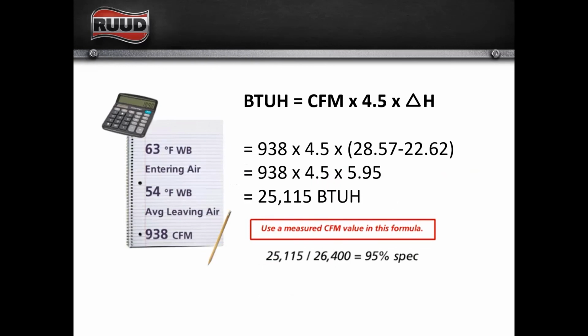So 938, we're going to plug that into our formula, right? BTU per hour equals CFM times 4.5 times our delta H. So 938 measured CFM times 4.5, which is our constant, times 5.95. And again, we got that 5.95 from subtracting 28.57 minus 22.62. If you forget to convert wet bulb to enthalpy and you put your wet bulb numbers in there, your number is not going to make sense to you. It's not going to add up properly.